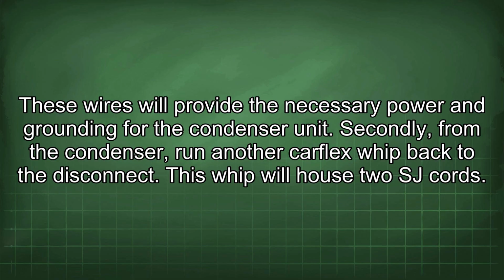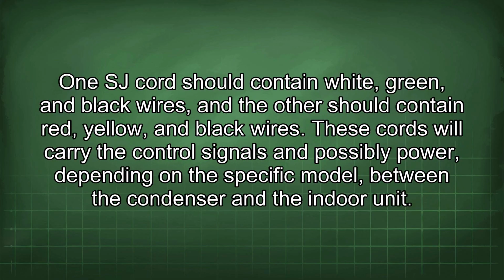Secondly, from the condenser, run another carflex whip back to the disconnect. This whip will house two SJ cords. One SJ cord should contain white, green, and black wires, and the other should contain red, yellow, and black wires.